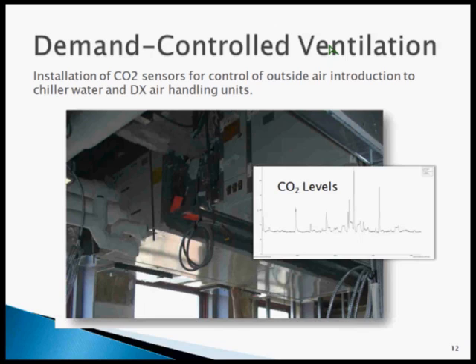...to 5 p.m., do you think every space that might have a person, that an engineer has painstakingly designed the VAV boxes and the outside air system to get 20 CFM per person to that spot? Do you think they're always there? Right. But the number of persons computed by square feet per person. Right. Not by number of workstations. Right. Yeah, Tom brings up a good point. Not only the occupancy change, but where the occupancy is, based on just generic design principles.